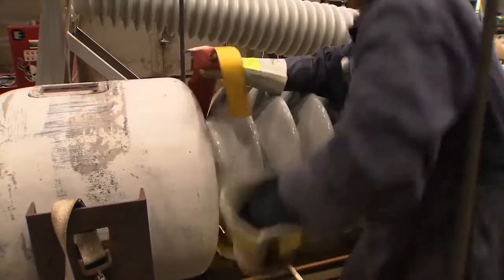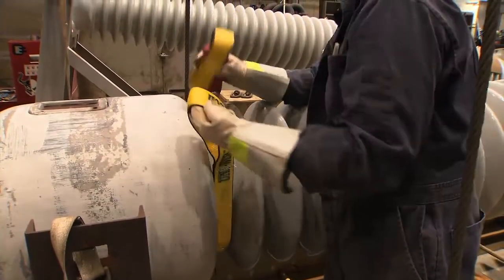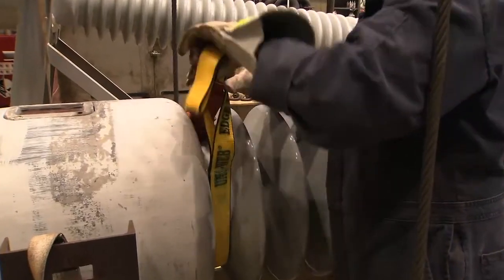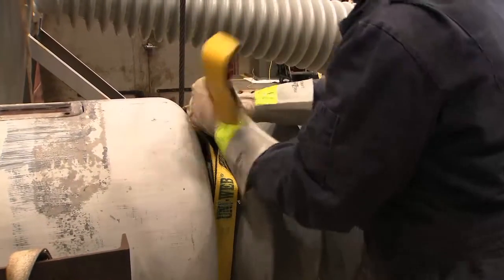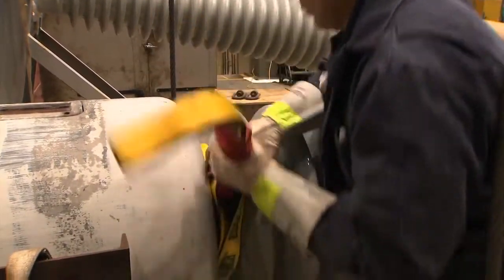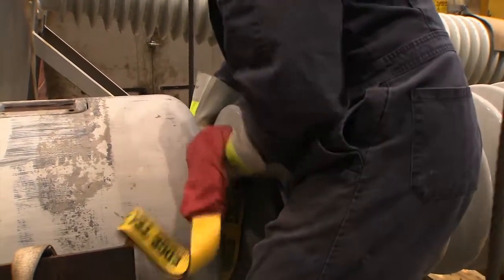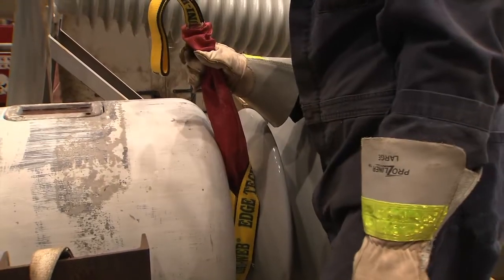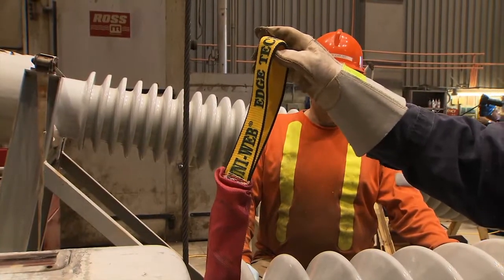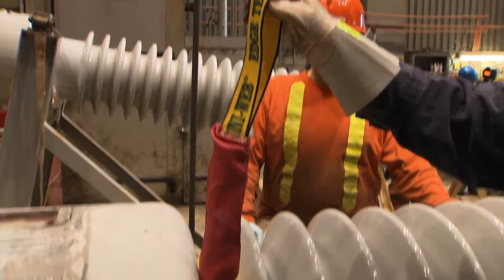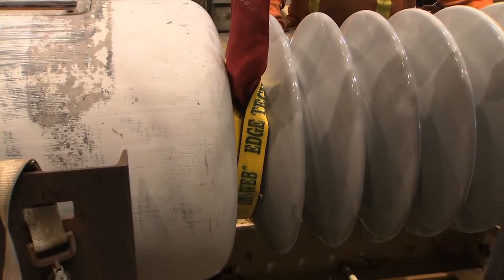Choke a sling around the porcelain directly below the oil reservoir tank and the top shed of the bushing. Choke the sling by first wrapping it around the bushing, and then inserting one end of the sling through the loop on the other end, and then pulling to tighten it securely around the bushing. The cables on the electric portable hoist will be attached to the sling choked around the top of the bushing.